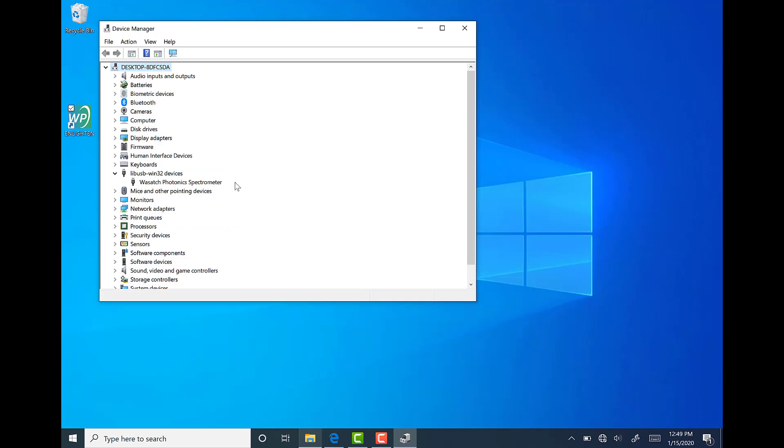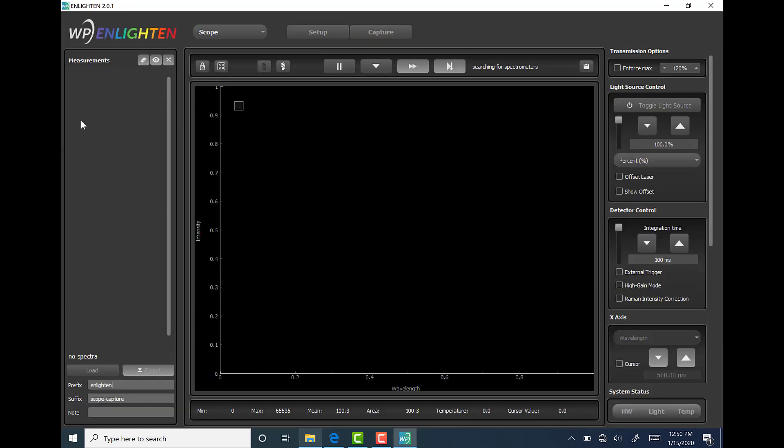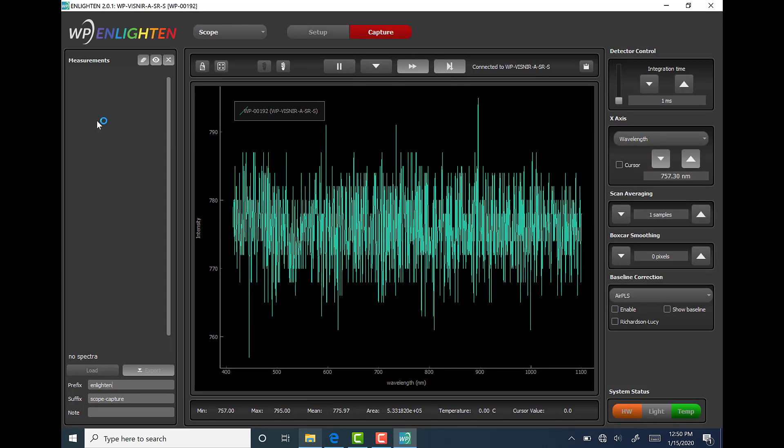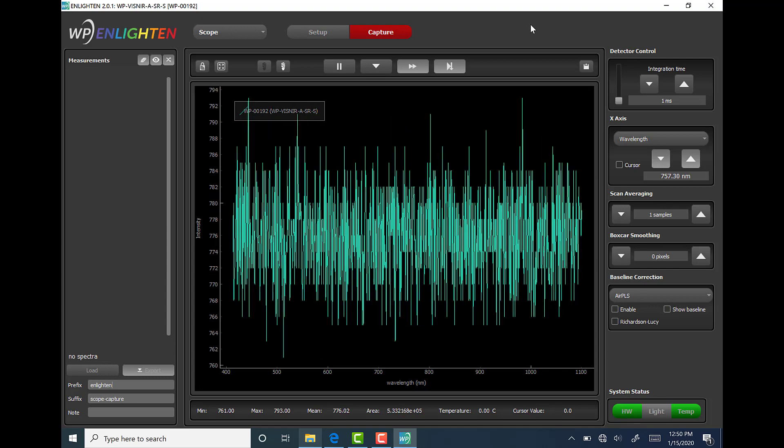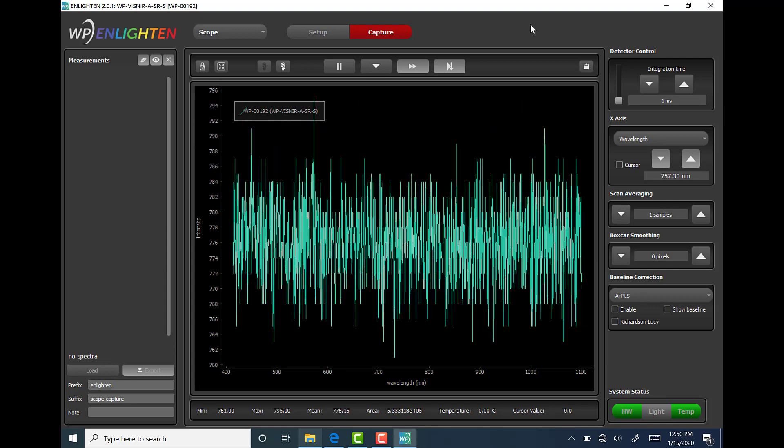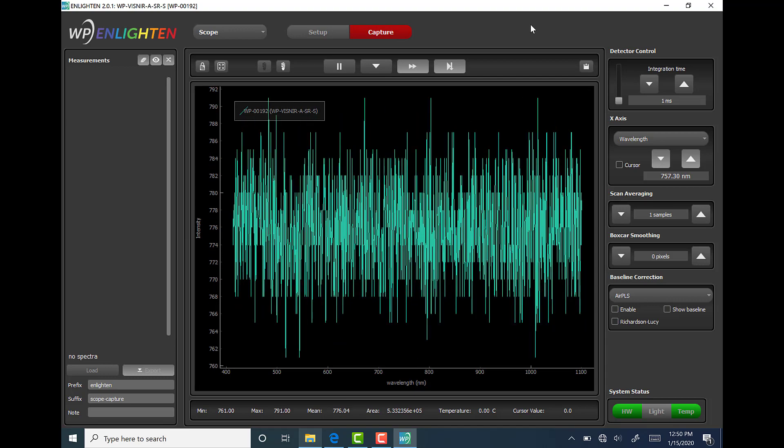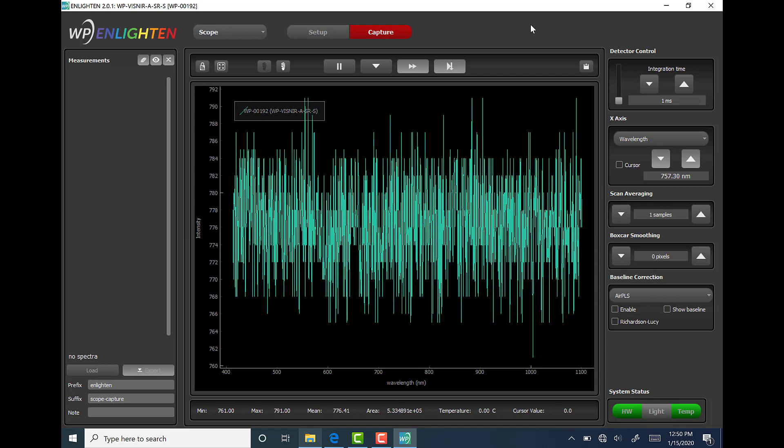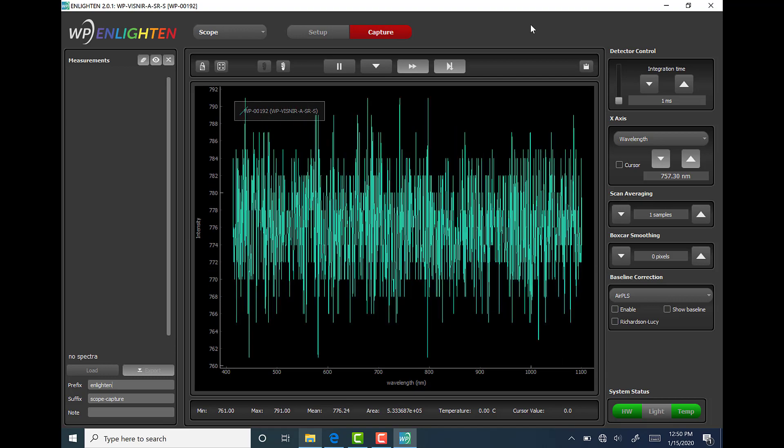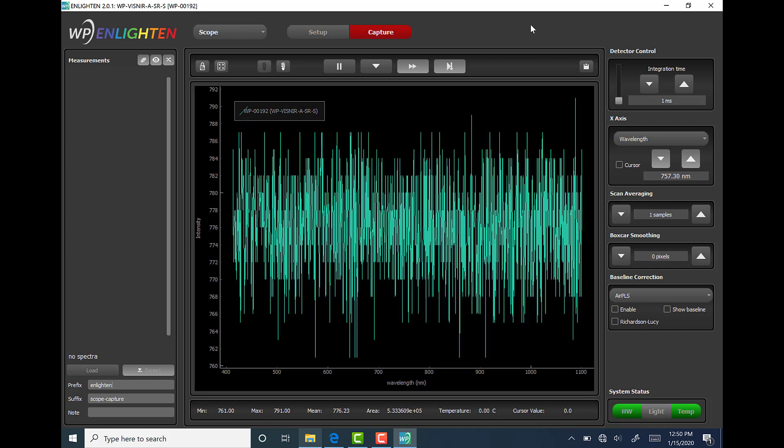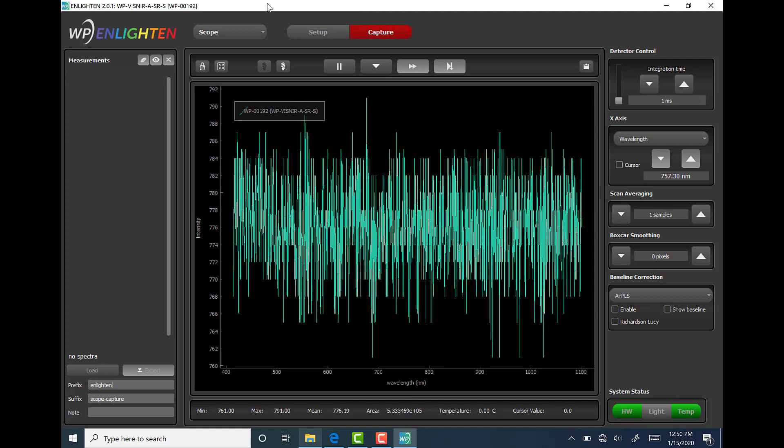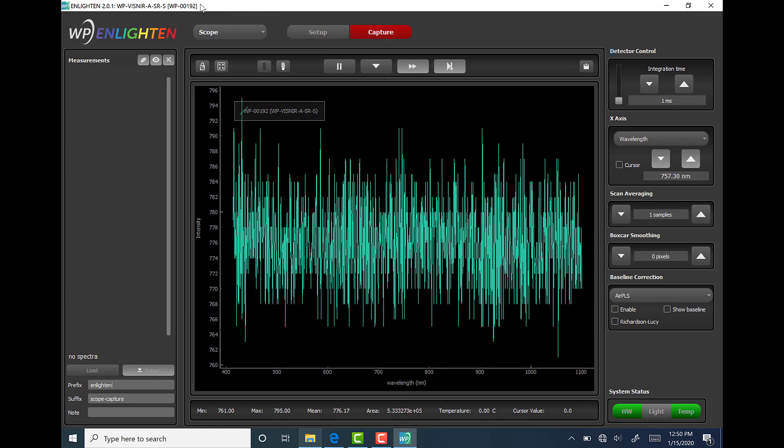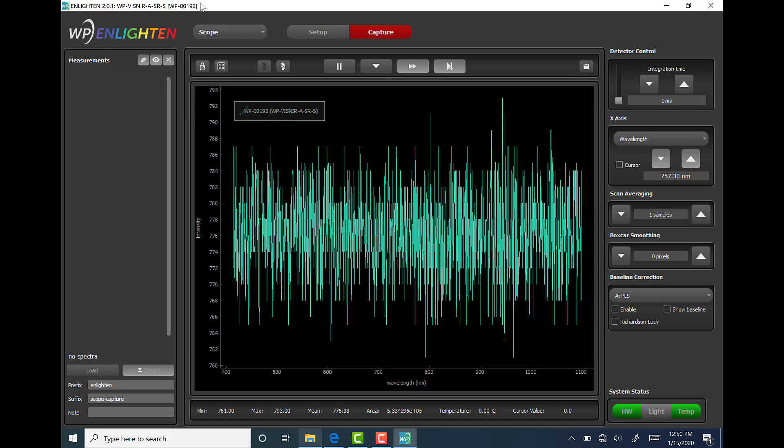After these sanity checks, we can launch the Enlighten software by double-clicking on the Wasatch Photonics icon on your desktop. The default mode that is open is called Scope Mode, specifically referred to as Scope Capture in the remainder of these videos and in the manual. This mode allows the user to view and obtain counts directly from the detector and offers a way to ensure the experimental setup is appropriate when the user is ready to start collecting meaningful data. Please keep in mind that counts are displayed in completely arbitrary units.